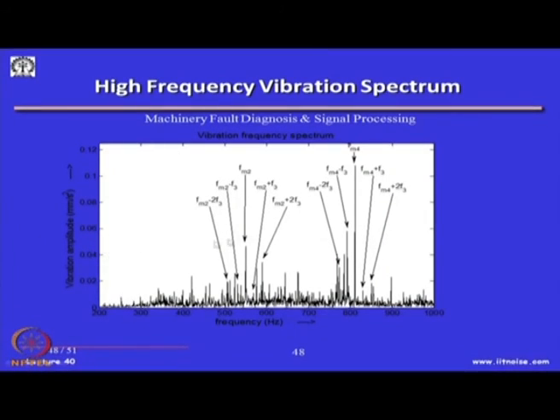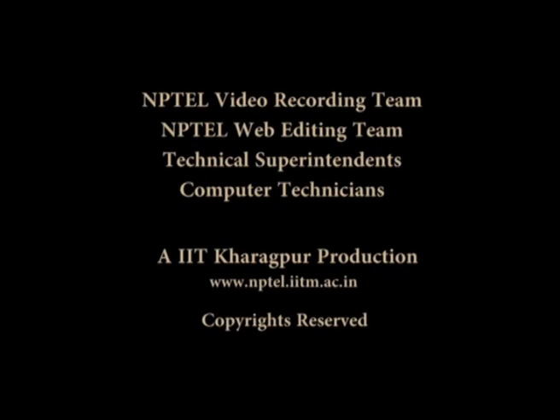These speeds are not varying much — even 0 to 3 rpm — but if for a fraction of a second this small variation is present because of a fault, and if that can be captured, it gives us a telltale sign as to what is defective in the system. This has been very popular with IC engines, and at our laboratory at IIT Kharagpur we have been using them to find out faults in gearbox systems. They are a cheap replacement to normal vibration measurements by rotational laser vibrometers — laser vibrometers cost millions of rupees whereas this costs only a few thousands of rupees. With this I would like to conclude this course on machinery fault diagnosis and signal processing. Hope you had an enjoyable teaching and learning lesson in this class. If there are any issues you can contact me over email or at my website or my phone numbers. Thank you.